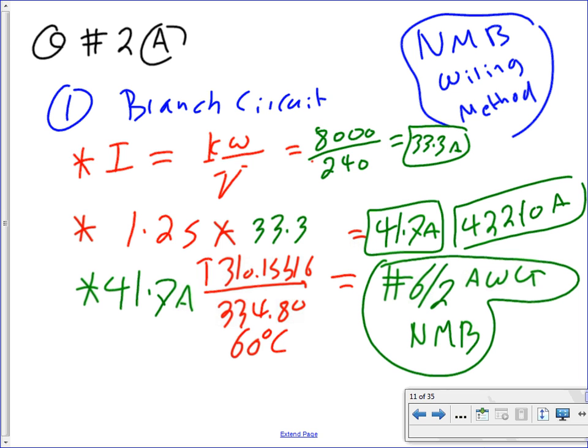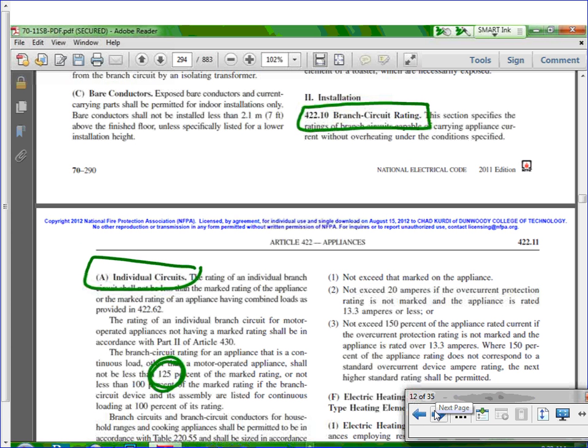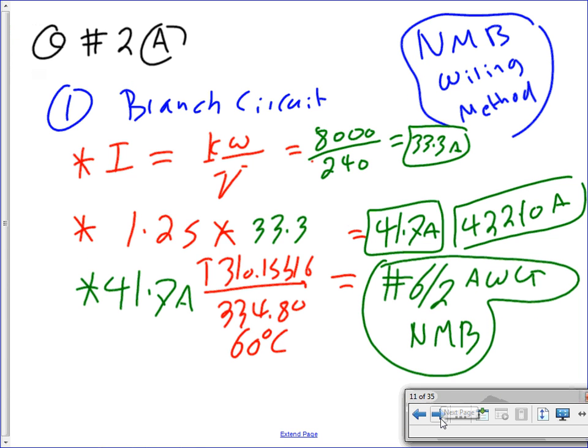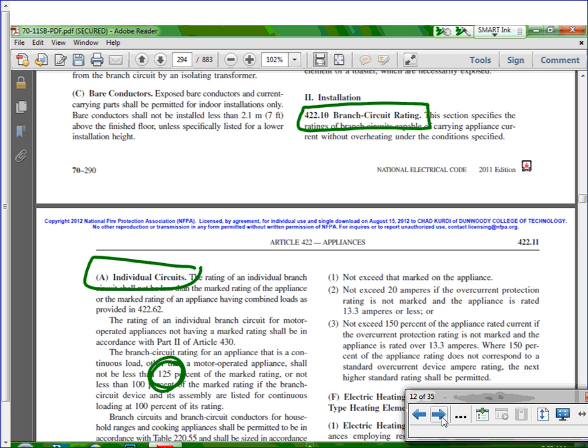Here's where we got that 125, guys. Here's where individual, can you guys see that's for appliances? And on appliances, that's where it got to 125. Your reference for 125, 422.10, it's an appliance. When you size it based on 125. I copied these ones for you. Any comments? Let me know when I can move on. Good? Yes? No? Okay. So here's your cable. Here's where you reference where you get the 1.25.